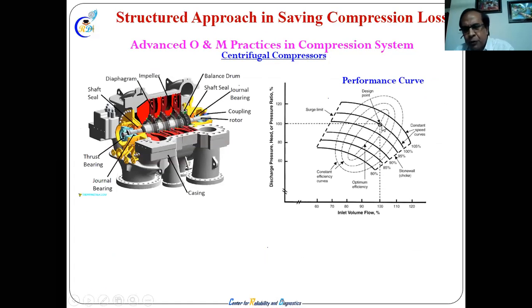So the performance curve should be such that it does not go beyond the surge limit, and it should not go above stone walling. Okay, there's a different thing. Those who know compression systems and anti-surge systems are aware of this surge limit and stone wall. We have to run this machine within this performance curve.